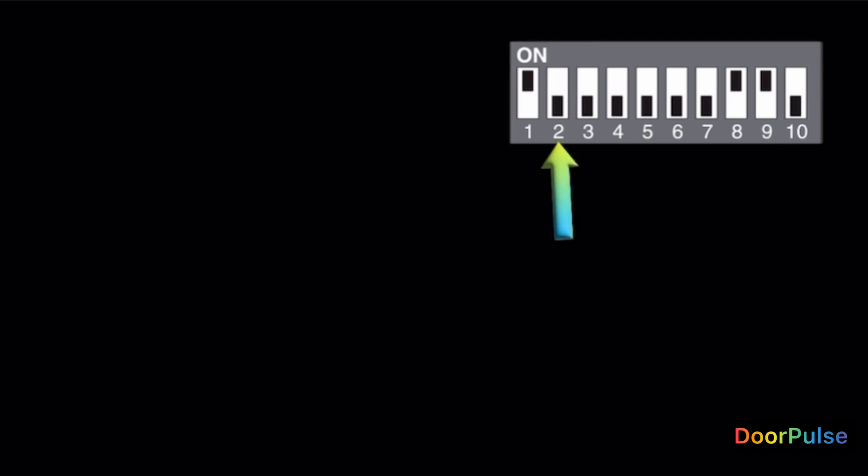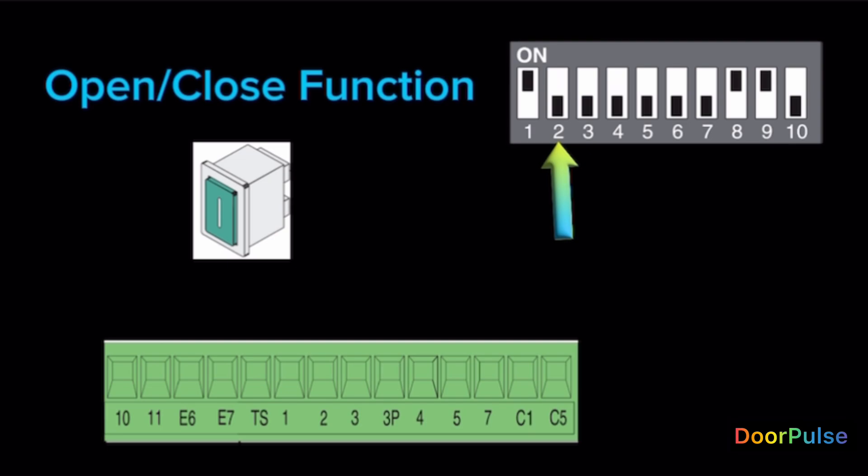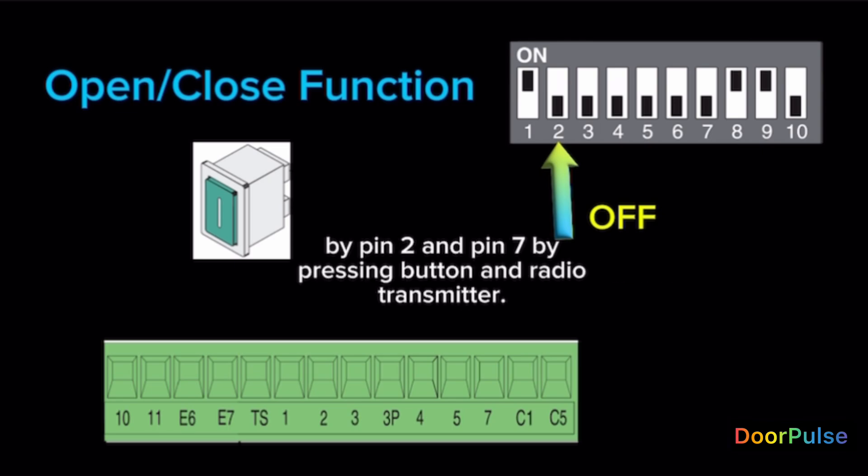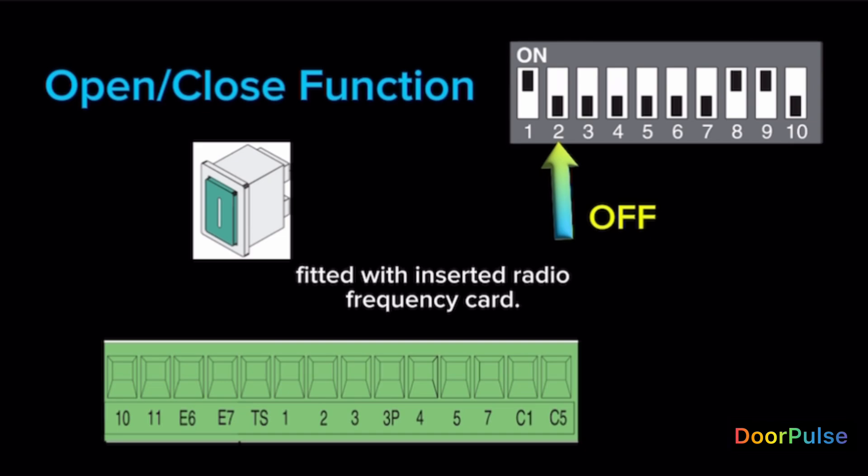Switch 2. Open and close function with pin 2 and pin 7. Switch 2 OFF. Just open and close function. Activate by pin 2 and pin 7 by pressing button and radio transmitter fitted with inserted radio frequency card.